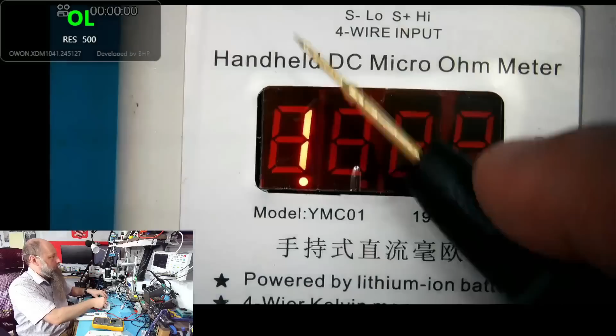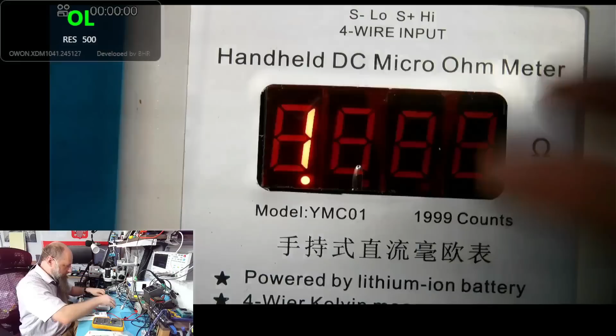Not good at all. It looks like it's dirty. So two problems with this probe. First of all, the cable, and second, the resistance. Resistance way too high. I don't think there's even a point in measuring frequency, but let's do it just for the heck of it. It's a little closer by 1 hertz.